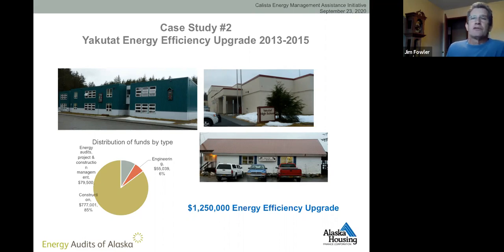Both schools were served by a heat recovery system from the power plant, which was 20 to 30 years old. There was no backup heat in either building, so if the heat recovery system failed, the buildings would have no heat - that's a problem. The high school was at the end of the waste heat loop, so on the coldest days there was insufficient heat; there just wasn't enough being generated.